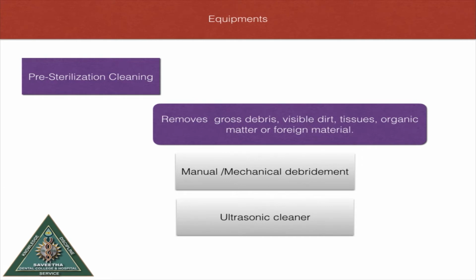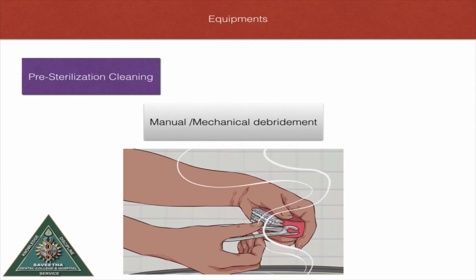Pre-sterilization cleaning removes gross debris, visible dirt, tissues, organic matter or foreign material from the instrument. It can be done either by manual debridement or an ultrasonic cleaner. Manual debridement involves the use of a long-handled brush and scrubbing the instrument, paying particular attention to the hinges of the instrument.